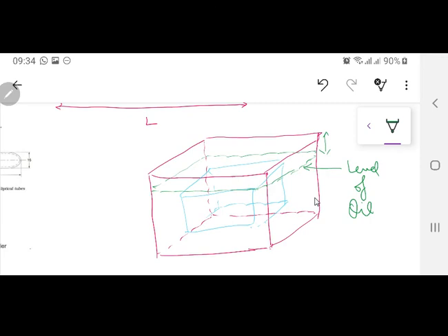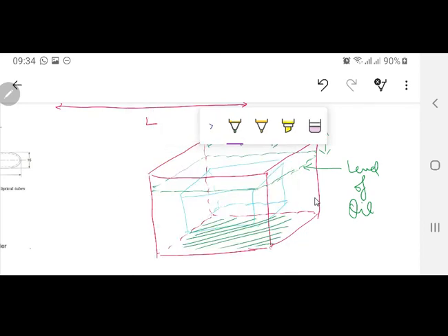Plus the top surface, you are going to have bushings over here, you are going to have the winding connections and all that stuff over there. So the top surface area is not going to dissipate any heat. The same answer is for the lower bed. This lower bed is not directly in contact and there is some wedge or some wooden material placed over there, so it's also not dissipating any heat. So the only area which is actually going to dissipate the heat is the side walls.